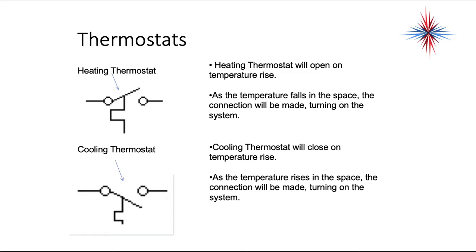Thermostats are found all over, not only in the conditioned space on a wall someplace, but they're used internally in the equipment as well. They are sometimes a safety device or an operating control. A heating thermostat will open on temperature rise. As the temperature falls in the space, the thermostat comes back down and makes a connection turning on the system.